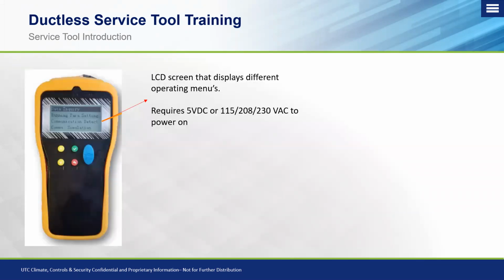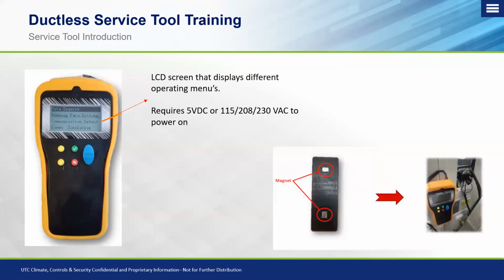So you'll see your LCD screen that displays different operating menus. It requires either a 5-volt DC power or a line voltage power, depending on whether you're dealing with a 115-volt system or a 208, 230-volt AC system to power it on. Now you'll see on the back side here, there's 2 magnet clips, which make it really nice because you could just put it right against the unit, plug into the system, and now you can start getting your data depending on what you're trying to access out of the system.